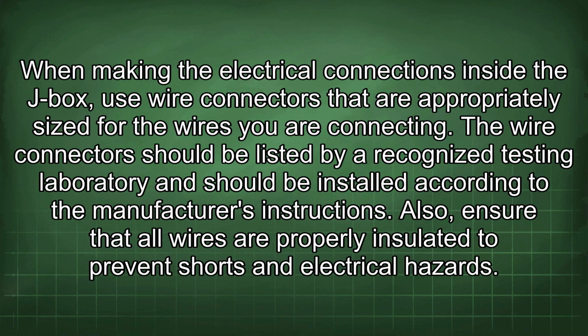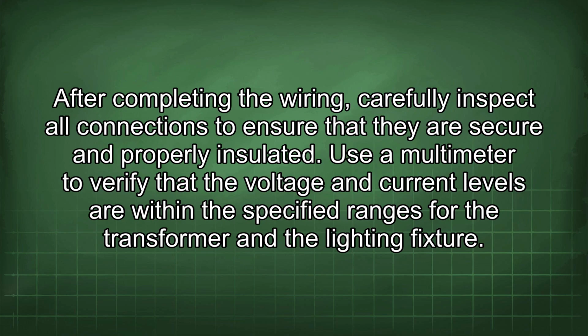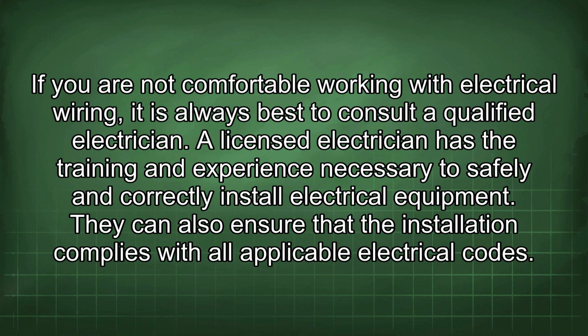When making the electrical connections inside the J-box, use wire connectors that are appropriately sized for the wires you are connecting. The wire connectors should be listed by a recognized testing laboratory and should be installed according to the manufacturer's instructions. Also, ensure that all wires are properly insulated to prevent shorts and electrical hazards. After completing the wiring, carefully inspect all connections to ensure that they are secure and properly insulated. Use a multimeter to verify that the voltage and current levels are within the specified ranges for the transformer and the lighting fixture. If you are not comfortable working with electrical wiring, it is always best to consult a qualified electrician. A licensed electrician has the training and experience necessary to safely and correctly install electrical equipment. They can also ensure that the installation complies with all applicable electrical codes.